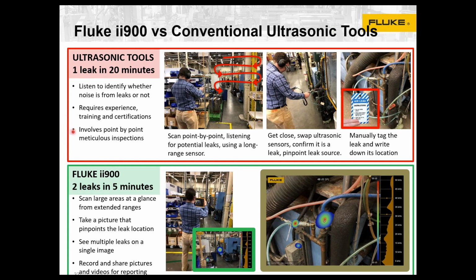It also requires that you go point by point. So you need to move up very close to all of the fittings, hoses, and quick connects, and there may be some challenges with that. Not only that, but we found that ultrasonic information, like sound, when it's emitted, goes in all directions and bounces off of surfaces. So how do you know whether it's an actual leak source or whether it's a reflection? So a lot of time is spent performing this activity, and it also requires experience and training.